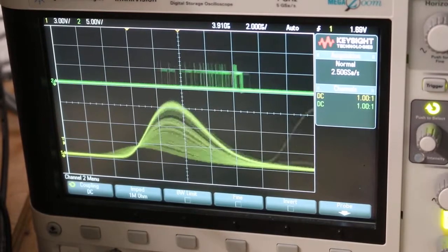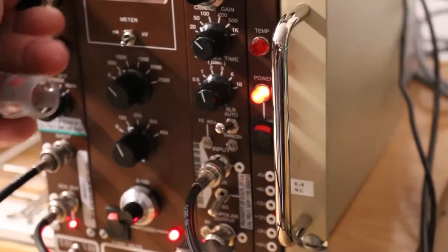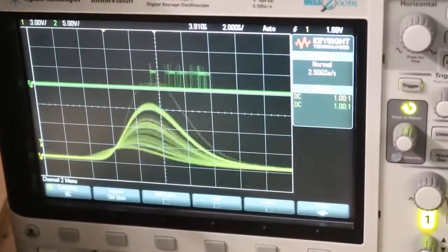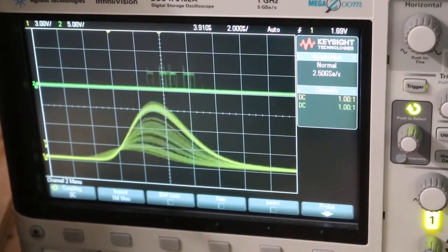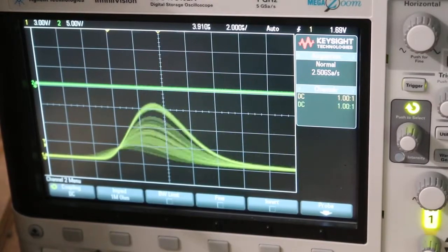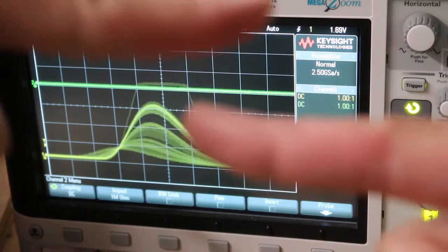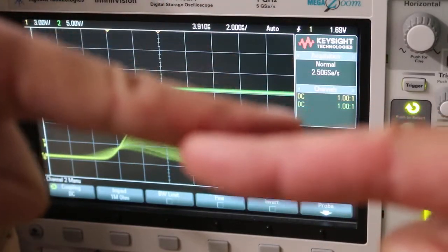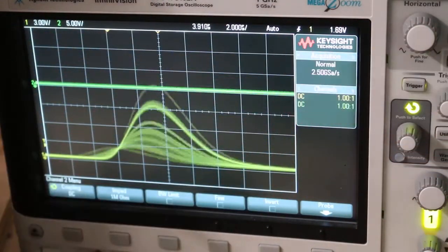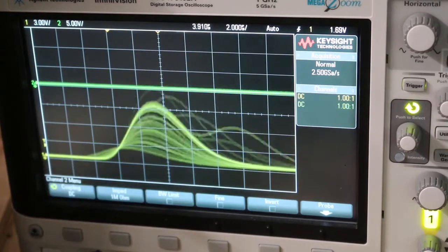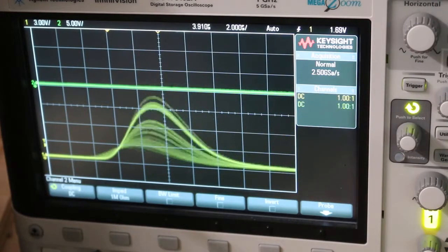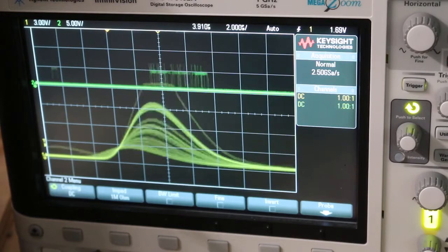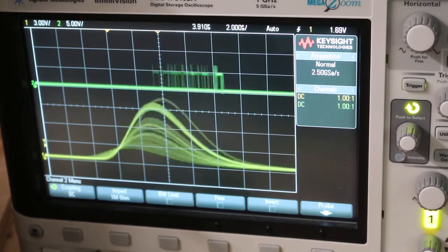Okay. And so I could also mess around with the upper level a little bit, and that's the knob up here. Let me just turn that upper level all the way down. What happens is it really puts a squeeze on those voltages here. They all disappear because now probably what I've done is I have one level right here and the upper level right here, and maybe they either look like that or even the upper level is below the lower level, and nothing can satisfy that, so all the green pulses are gone. So typically then I'm just going to open up that upper level all the way once again, and only do my discrimination based on that lower level setting.